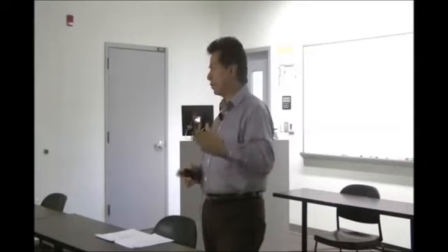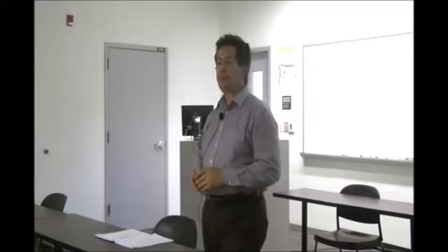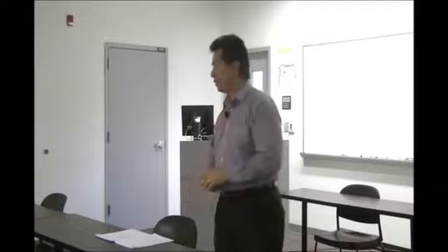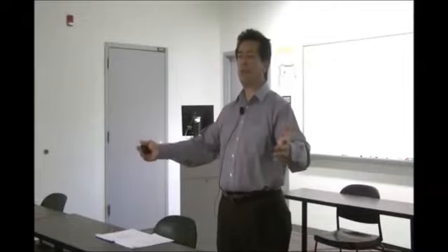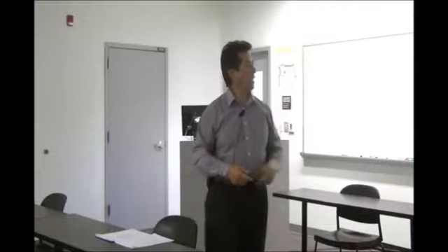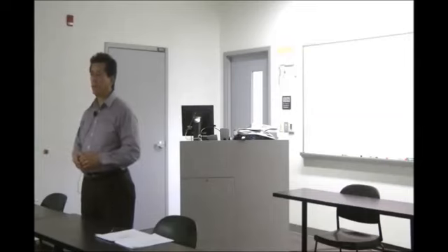But you trace it back, my controls could not handle 2 more. I was right at the jagged edge, which meant I had to bring in another panel. Well, that panel was $15,000. So guess what? I've got a new panel with 2 additional connections, and I got 24 left over. So I've got capacity now, don't I? Which is a good thing. Now I can move on into the future. But one item that you've got to ask: can the existing control systems support what you're planning to do? Because again, these are hidden costs.